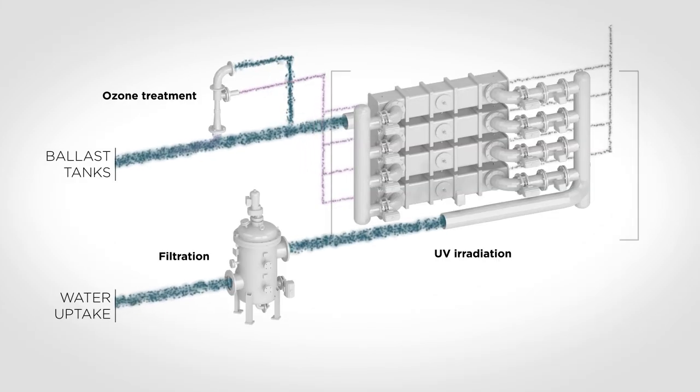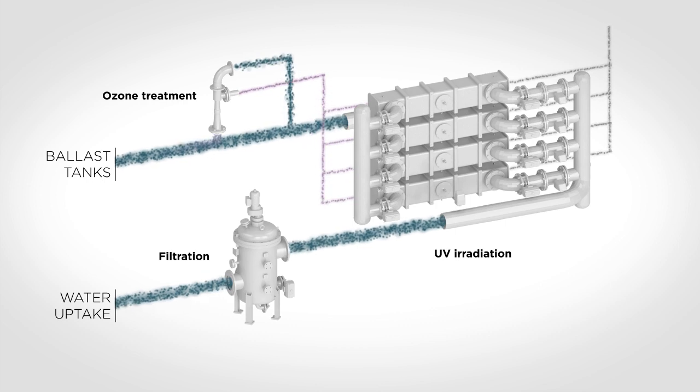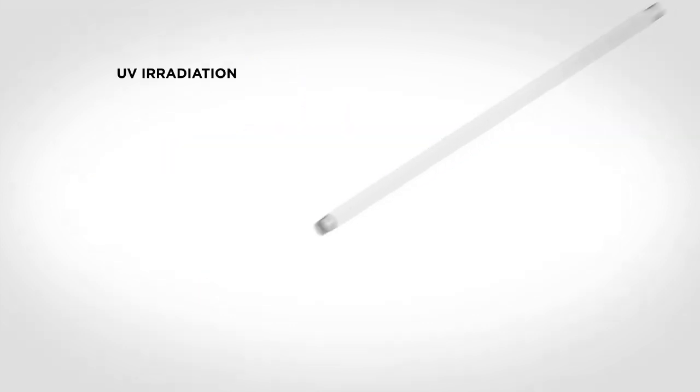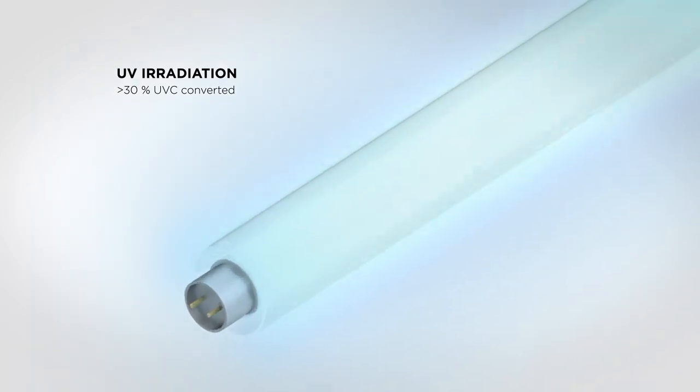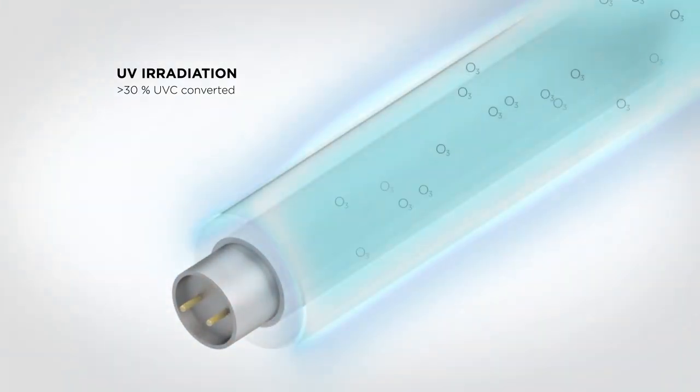The second treatment step is UV irradiation with low-pressure lamps. The advantage of low-pressure UV lamps is that more than 30% of the energy to the lamps is converted into UV-C, which makes the organisms non-viable.